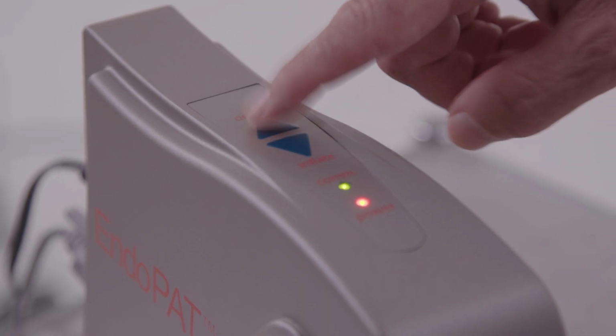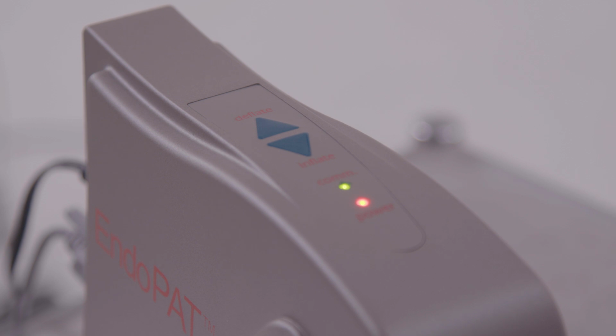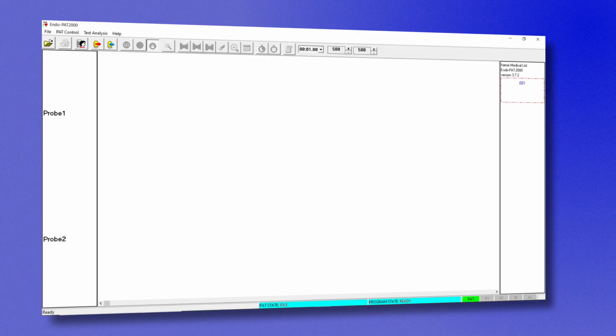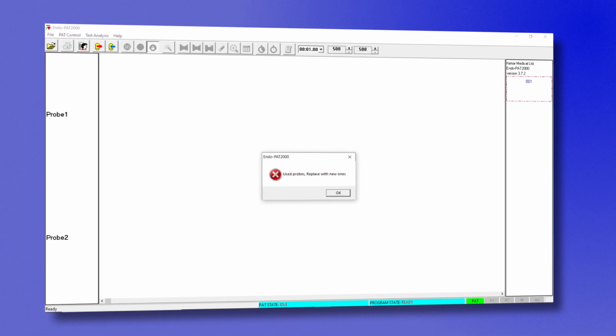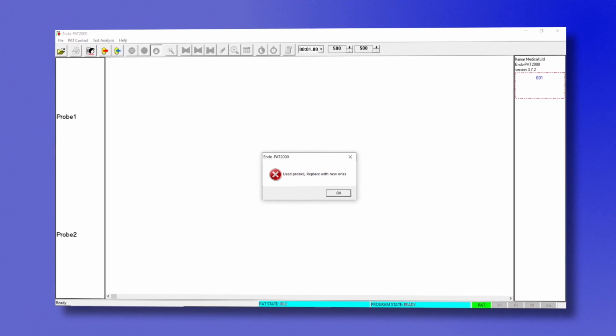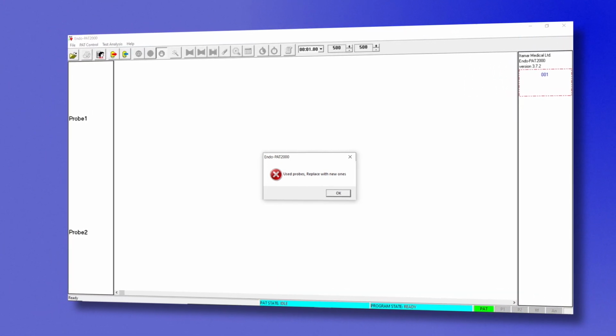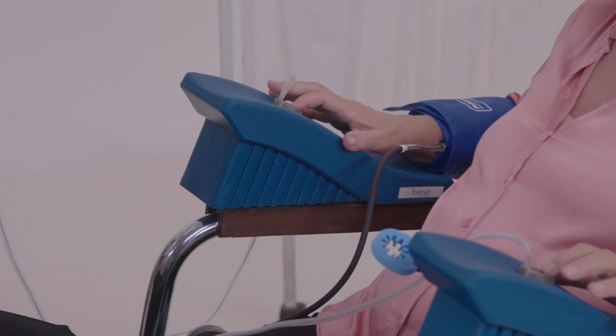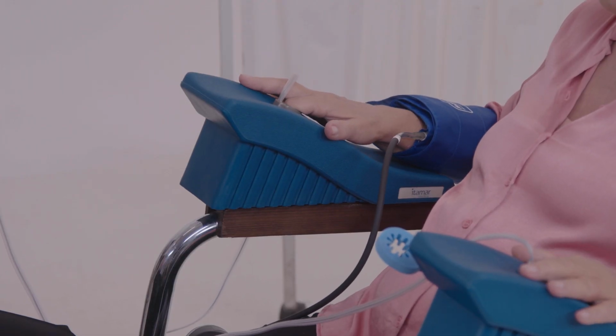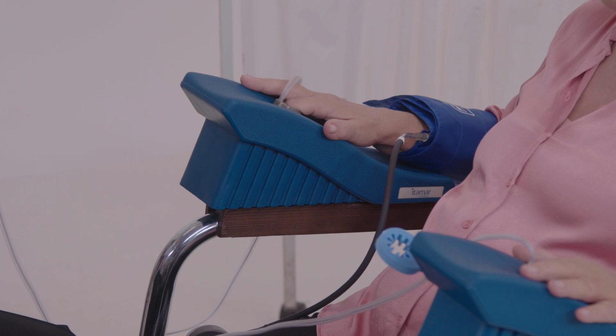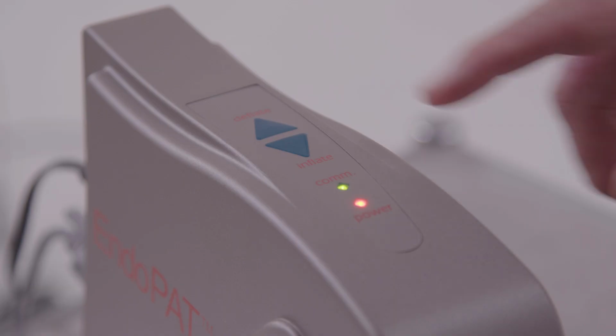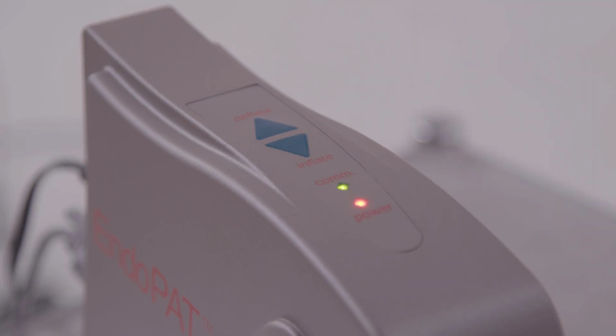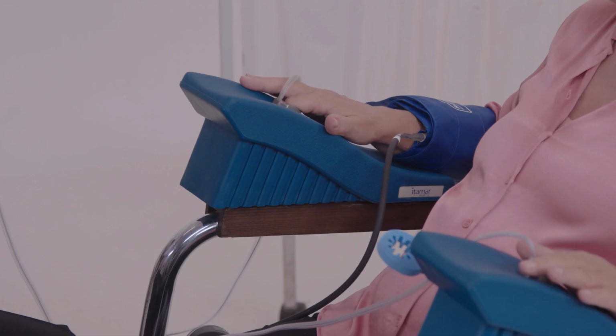Fully deflate the probes by clicking the icon in the software or by pressing the deflate button on the device. If the probes are not new, a warning dialog box will open. Replace the probes with new probes. Place the selected fingers into the probes, making sure the fingers are inserted all the way to the end of the probe. Inflate probes by pressing the inflate button on the device or the software.